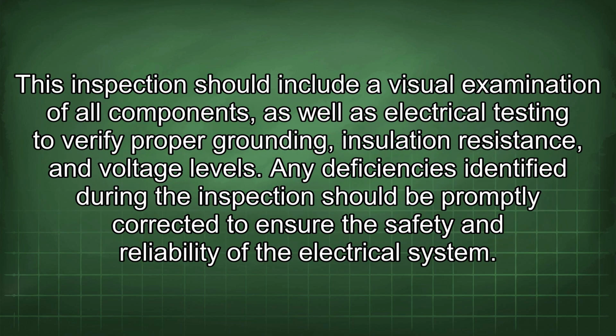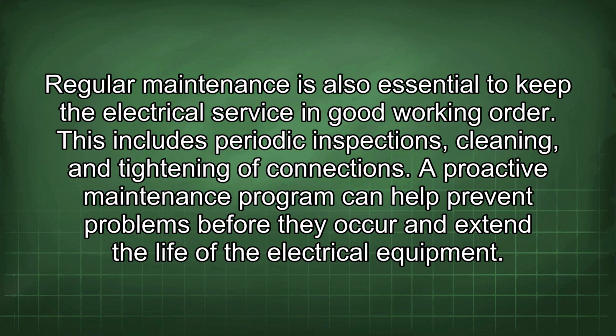This inspection should include a visual examination of all components, as well as electrical testing to verify proper grounding, insulation resistance, and voltage levels. Any deficiencies identified during the inspection should be promptly corrected to ensure the safety and reliability of the electrical system. Regular maintenance is also essential to keep the electrical service in good working order. This includes periodic inspections, cleaning, and tightening of connections. A proactive maintenance program can help prevent problems before they occur and extend the life of the electrical equipment.